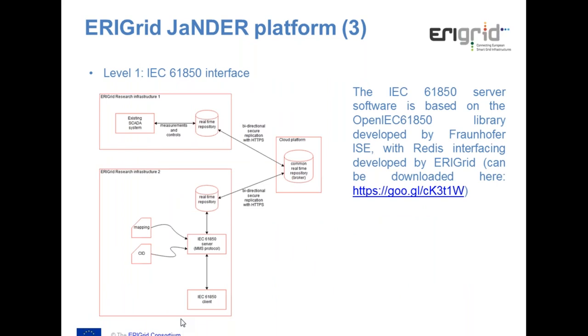The idea, as I already said, is to apply 61850 over this virtual bus. How does this work? You can see a quick sketch in this picture, in particular on the left-hand side. Each research infrastructure has its real-time repository, as I said before, related to the virtual bus. And on top of this repository, it can execute a 61850 interface, which connects to the real-time repository and exposes its contents, which are typically measurements and controls from a SCADA system, with the 61850 protocol.